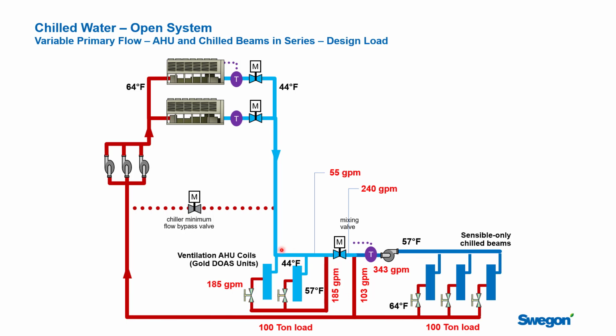Now this load, as we said before, is going to vary quickly with outside air. So as you go from design summer day to design winter day, this load's going to drop off. This one will drop off as well, but a lot slower than this one will, because the internal heat gains are more universal across that. So if your flow rates are good on a design day, you're already well on your way to being able to convince yourself that you could do this kind of system design, because this flow rate will be above the air handling unit flow rate during shoulder weather.